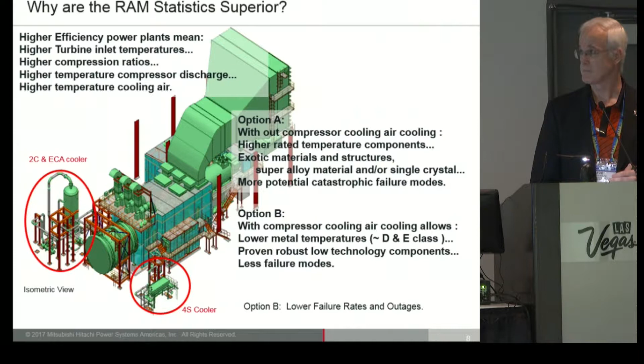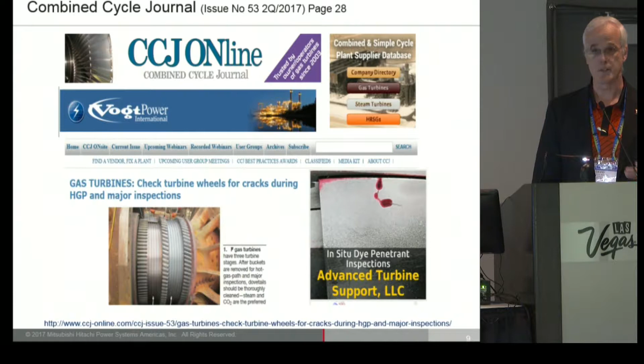Combined Cycle Journal, CCJ Online, put together this article: gas turbine checking turbine wheels for cracks during hot gas paths or major inspections. This highlights the point that I just made earlier about the materials. If you look down this article, which has the web link at the bottom, some of the salient points are that some of the F-class machines, which all the OEMs produced, have requirements that you thoroughly clean and check the discs every so often to make sure they're not cracking. That's the one failure mode I mentioned earlier from the insurers that talked about disc liberations. This is where it comes from.